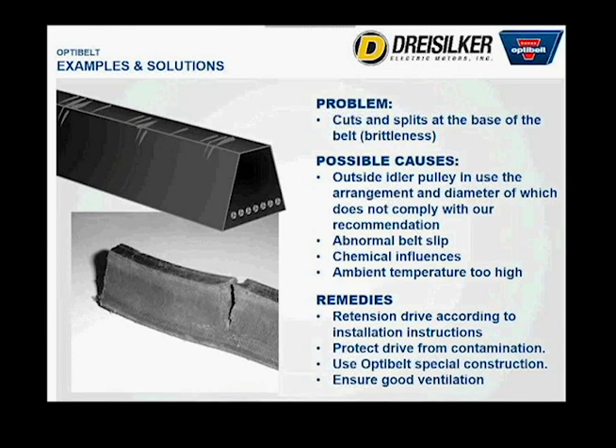Cuts and splits in the base of the belt, so brittleness, you can see these in really old belts, or it looks incredibly old, or ones that have been in a very hot environment. And when you start seeing these, that is usually how people determine it's time to replace the belt, meaning the rubber's getting old or it's reaching the end of its service life. So possible causes are an outside idler, but this isn't applicable to most air handler and HVAC situations, and only some belts can be used with outside idlers. Other ones, the rubber doesn't have the flexibility to bend both ways, both around the pulley and backwards. And what this does is it creates extra stress and extra heat, and eventually the belt just rips itself apart.